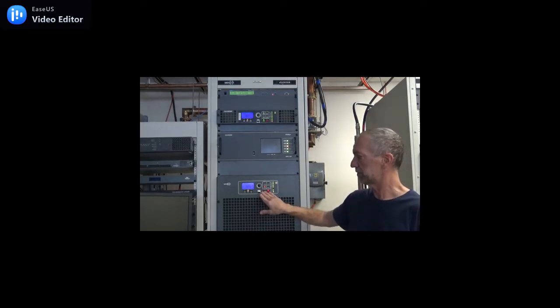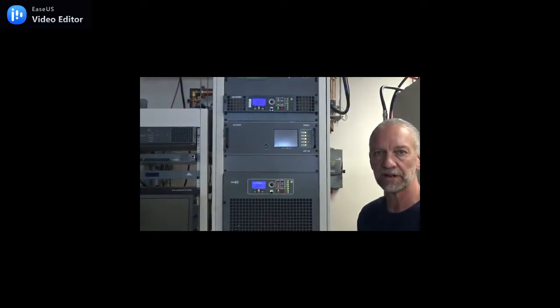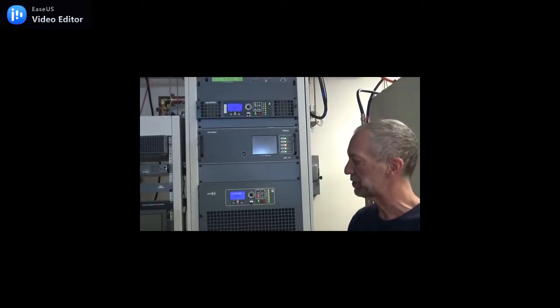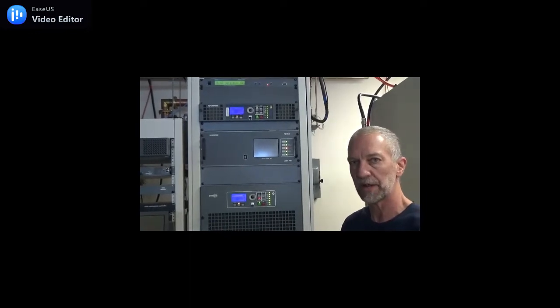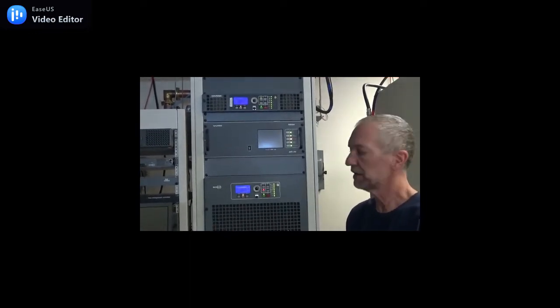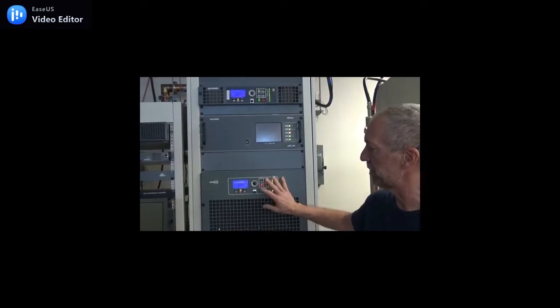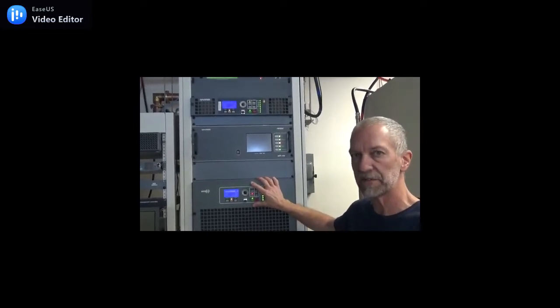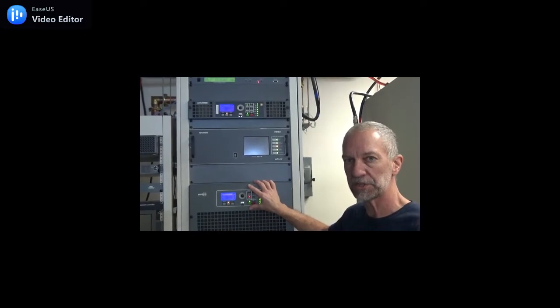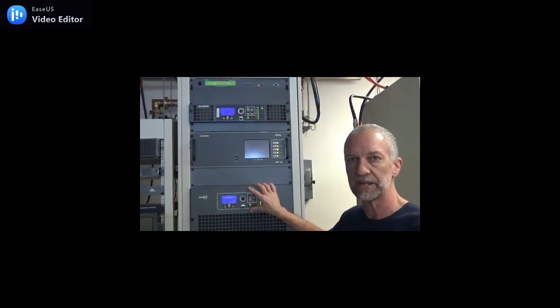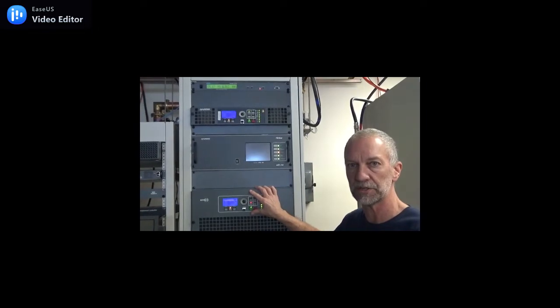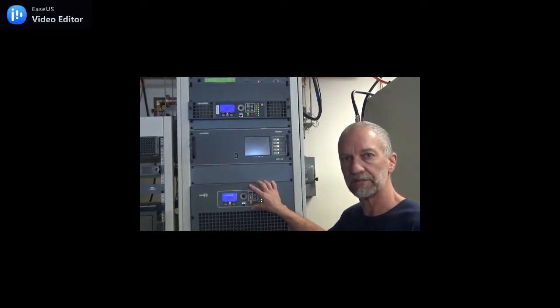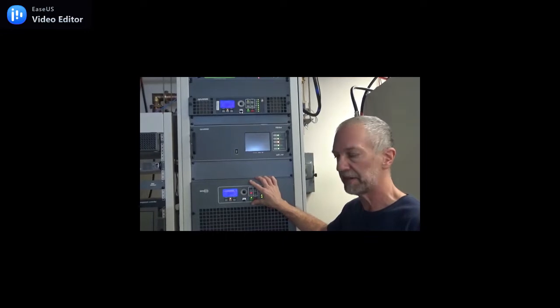So to do that, we're just going to simply turn the transmitter on. Okay, so we've had the transmitter running for 30 minutes. We've got the temperature on the module stabilized, so we're ready to start the calibration procedure. So again, just as a reminder here, you'll want to read section 5 of the manual, the calibration procedure, before you start this. It's always a good idea to read through each of the lines and make sure you understand the procedure. Also, obviously, looking at this video would be a benefit too.